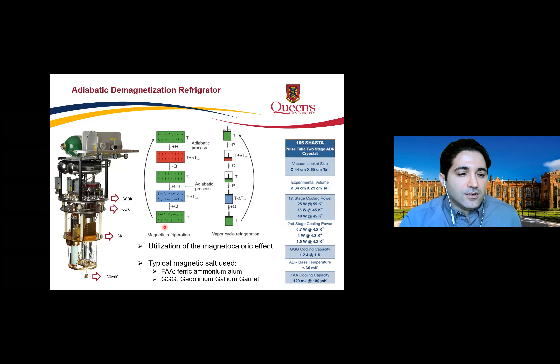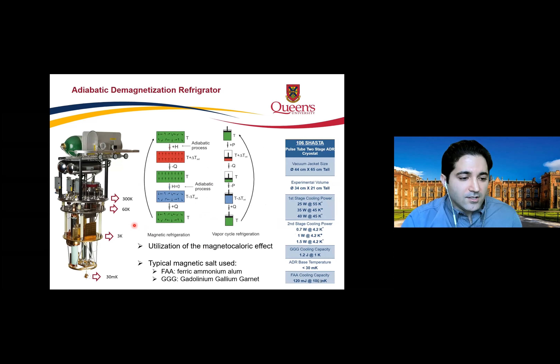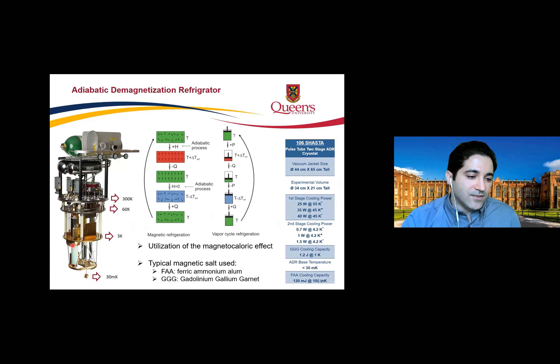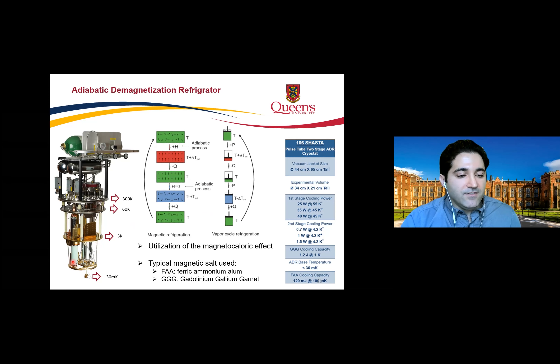Once mounted, you need a refrigerator to cool down to around 30–100 mK. There are adiabatic demagnetization refrigerators (ADRs) and dilution refrigerators. We had an ADR, and we were somewhat affected by its magnetic field — we later added a magnetic shield. The ADR cooling technique is based on paramagnetic salt pills like ferric ammonium alum or gadolinium gallium garnet, using a strong magnetic field of around one tesla.